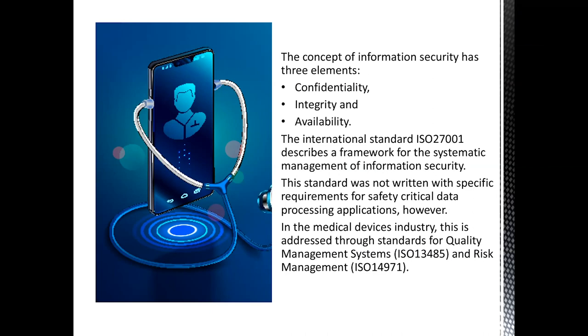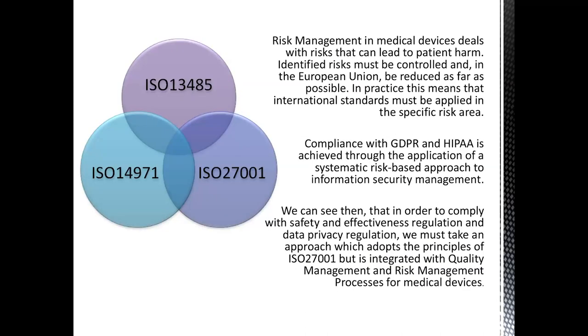But this standard was not written with specific requirements for safety critical data applications. So in the medical devices industry, this is addressed through standards ISO 13485 for quality management and risk management standard ISO 14971. So when I talk about an integrated approach, it's an integrated approach to risk management, information security, and quality management.